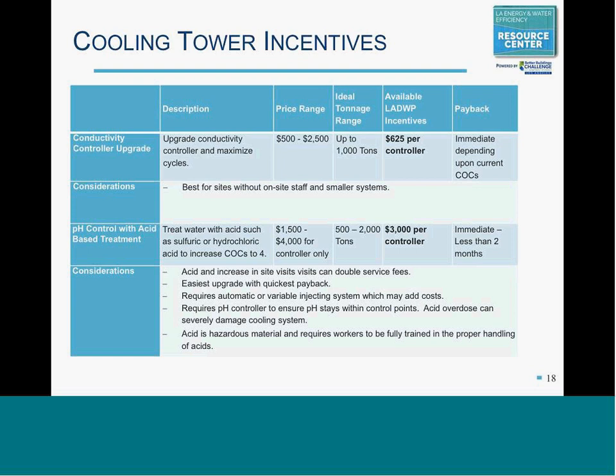Next is acid and partial acid treatment, sometimes called pH trimming. Acid is incorporated into the water treatment, increasing cycles even above standard treatment to 4 or 5 cycles. You'll install a pH controller, and DWP offers $3,000 per controller, with payback that should again be immediate. Careful consideration should be given to handling acid. Partial acid treatment is more convenient and less risky, and that's what most properties are moving toward.